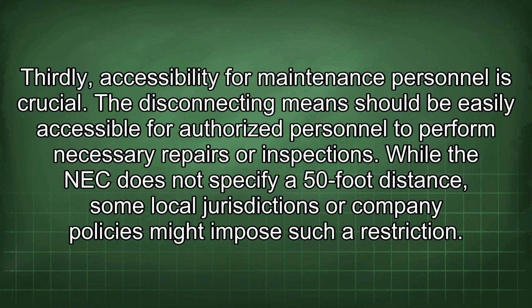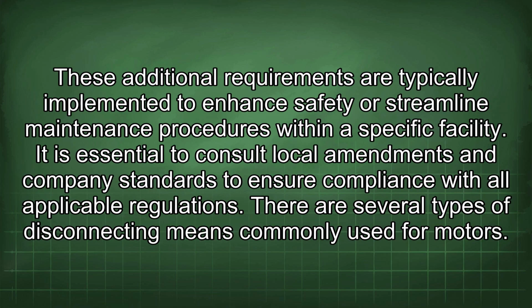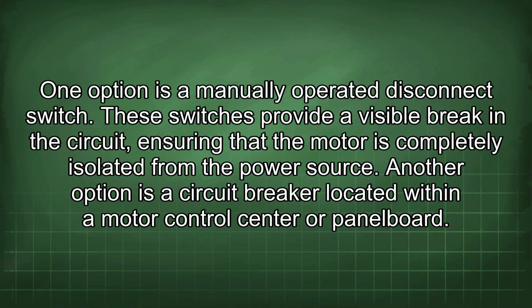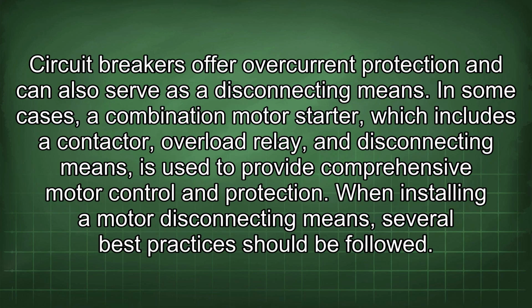While the NEC does not specify a 50-foot distance, some local jurisdictions or company policies might impose such a restriction. These additional requirements are typically implemented to enhance safety or streamline maintenance procedures within a specific facility. It is essential to consult local amendments and company standards to ensure compliance with all applicable regulations. There are several types of disconnecting means commonly used for motors. One option is a manually operated disconnect switch. These switches provide a visible break in the circuit, ensuring that the motor is completely isolated from the power source. Another option is a circuit breaker located within a motor control center or panelboard. Circuit breakers offer overcurrent protection and can also serve as a disconnecting means. In some cases, a combination motor starter, which includes a contactor, overload relay, and disconnecting means, is used to provide comprehensive motor control and protection.